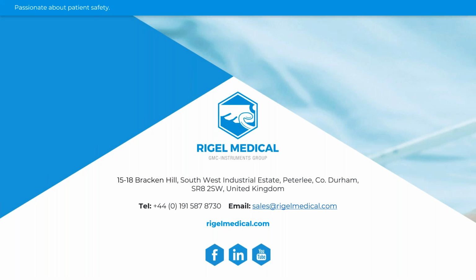Perfect. So, are there any challenges you've run into when trying to test AEDs, for example, with pads not being reusable or batteries being difficult to source? Yeah, that's definitely an issue. Batteries are very expensive. They can range from $150 up to $400. They're definitely not cheap, and every discharge is shortening the life of that, and that actually worsens the readiness of an AED in an emergency. So we need to limit the energy tests that we're performing, unless they're necessary. So sometimes that's either just post repair or during acceptance testing.